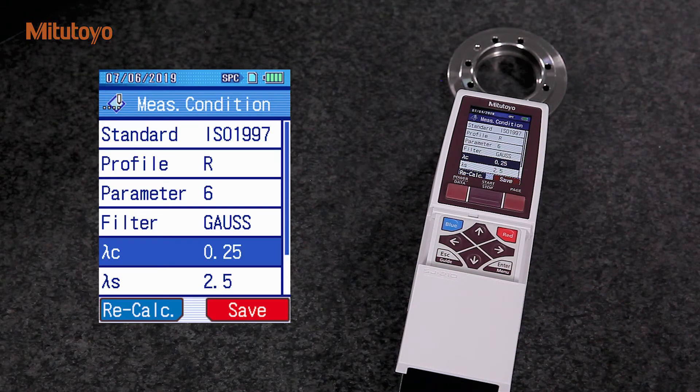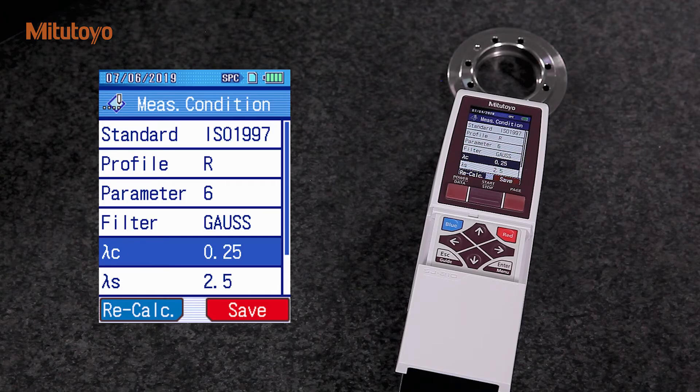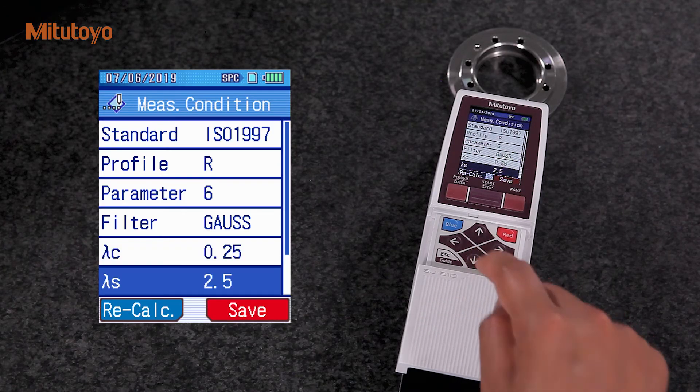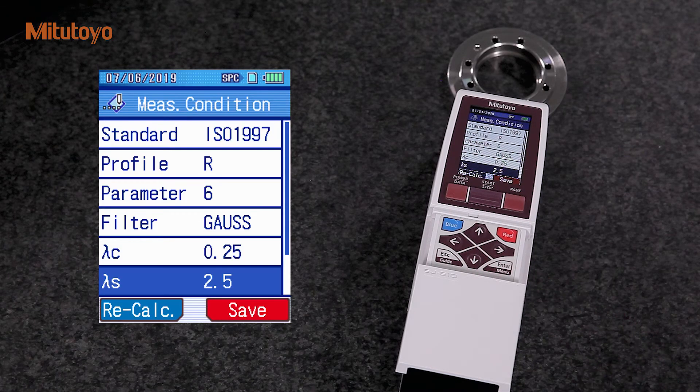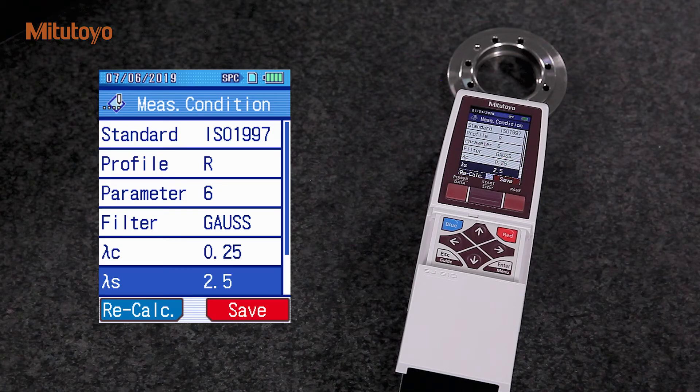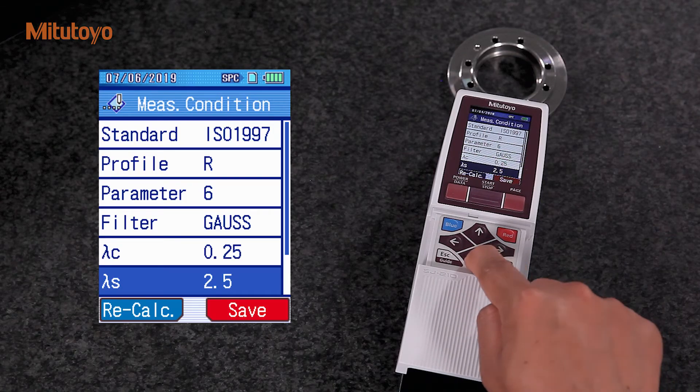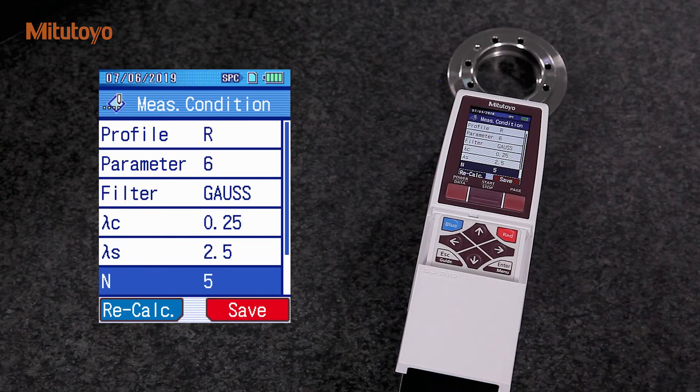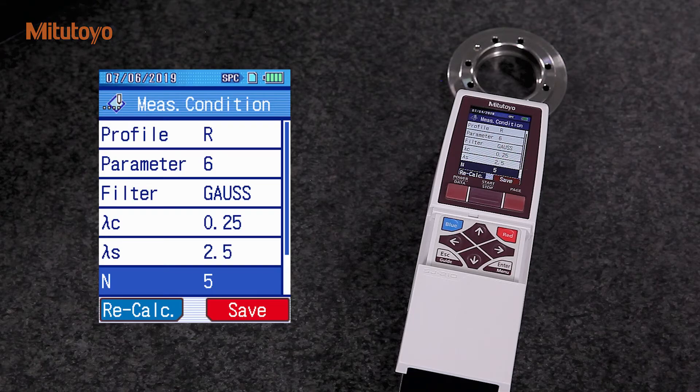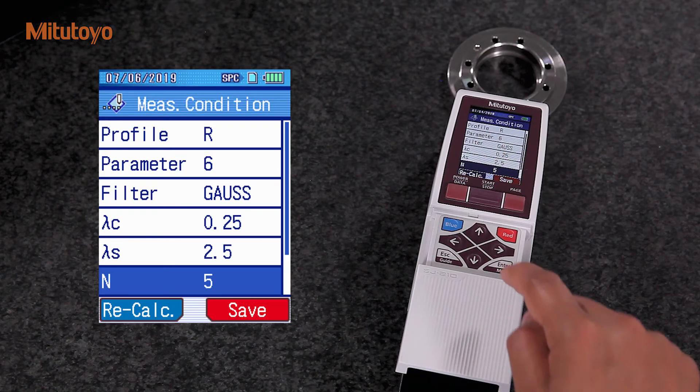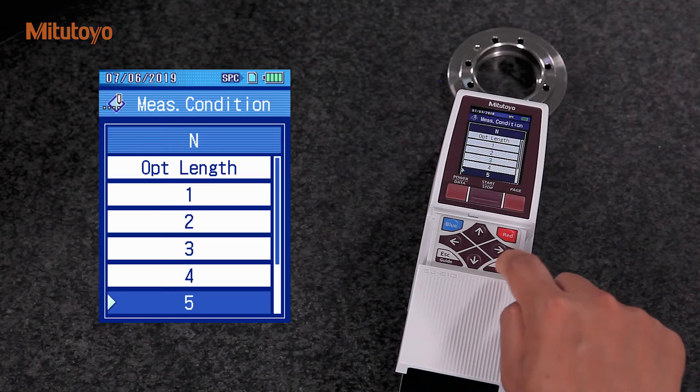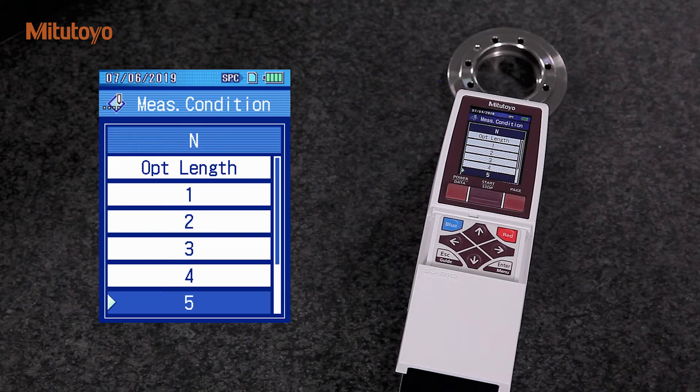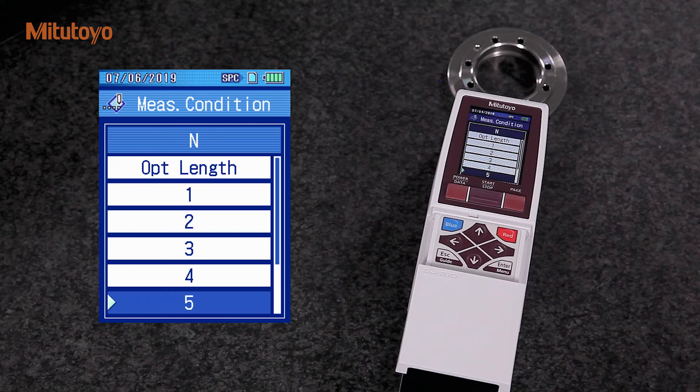The SJ-210 automatically chooses Lambda S according to our selected Lambda C. N is the number of our sampling length. According to the ISO standard, 5 is the default. However, it can be changed in the SJ-210.